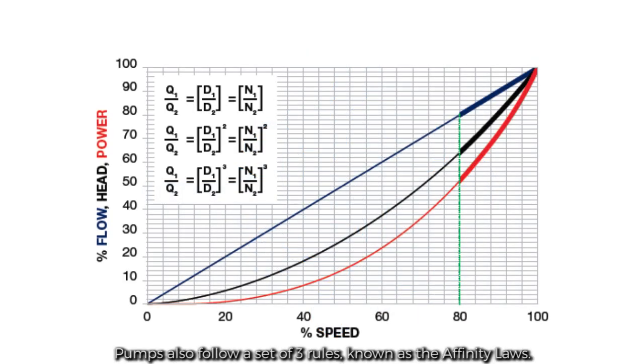Pumps also follow a set of three rules known as the affinity laws. Assuming the size of the impeller is kept constant, then the following statements are true: Flow is directly proportional to the speed, head is proportional to the square of the speed, and power is proportional to the cube of the speed.